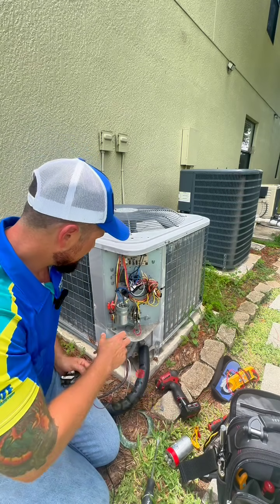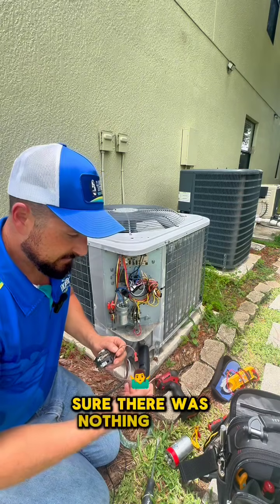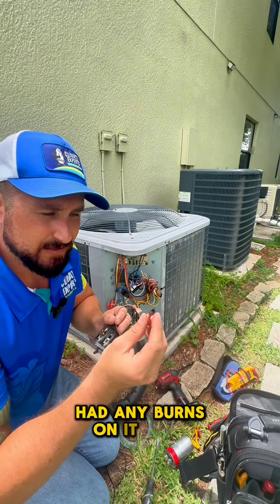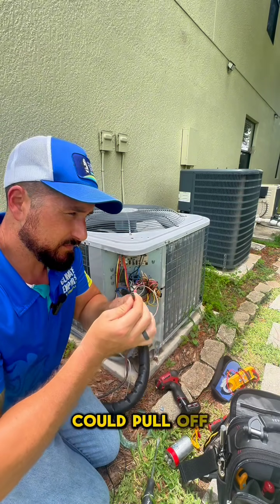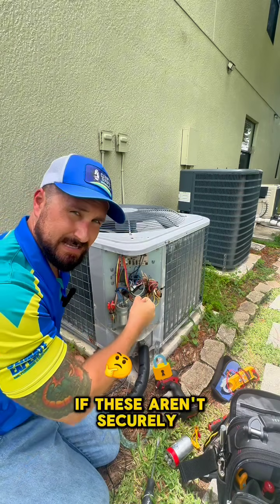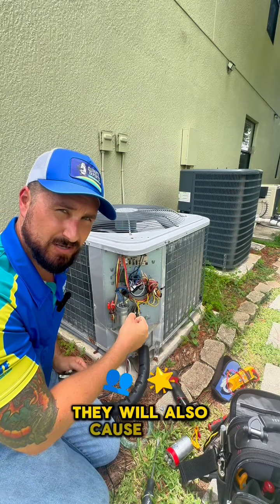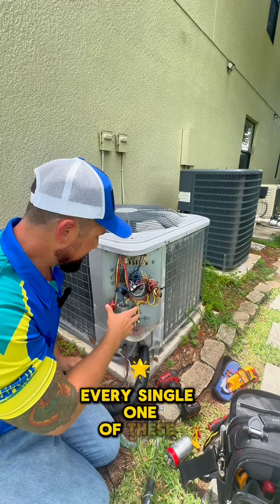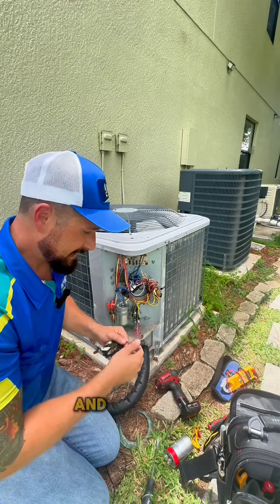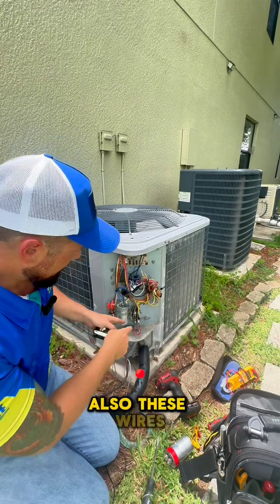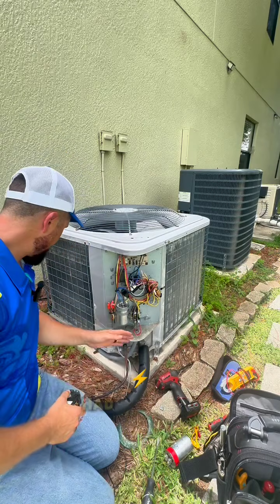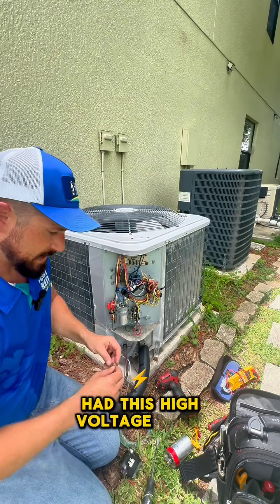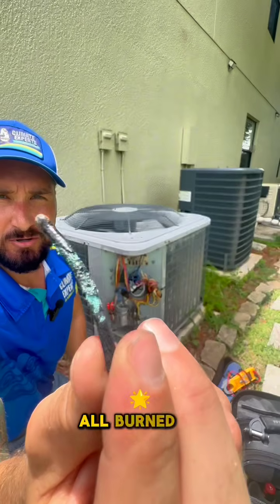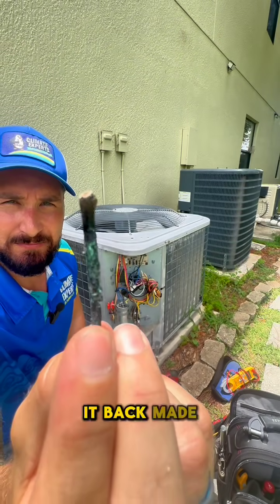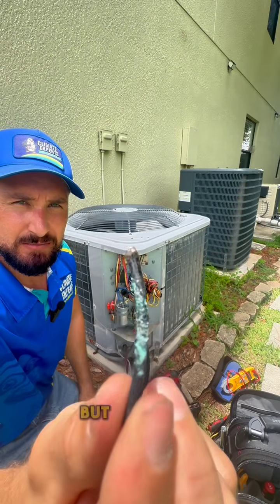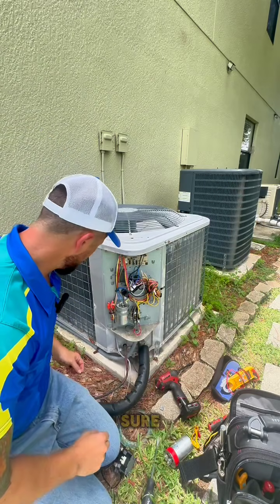I checked every single spade connector on here to make sure there was nothing that had any burns on it. Also, these get loose, so if these could pull off, that's not a good sign. If these aren't securely attached onto the spade, they will also cause it to arc. So we want to check every single one of these connectors to make sure that they're tight and nothing's already burnt. Also, these wires here, when we first came in, we had this high voltage wire was all burned up. So I went ahead and cut it back, made sure that we had clean copper. But these are the things that a professional will do to make sure that it's done right.